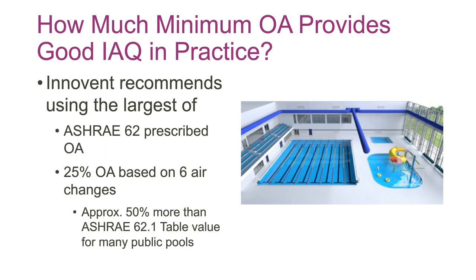So how much really should you have in practice for good indoor air quality? We recommend that you do the larger of the ASHRAE 62 tabled amount, or 25% of the outside air based on 6 air changes. It results in about 50% more fresh air than the table value for a lot of public pools. So instead of the 15%-ish, we're going to be at that 25% number.